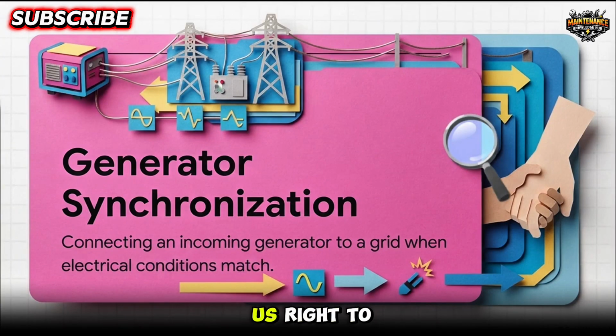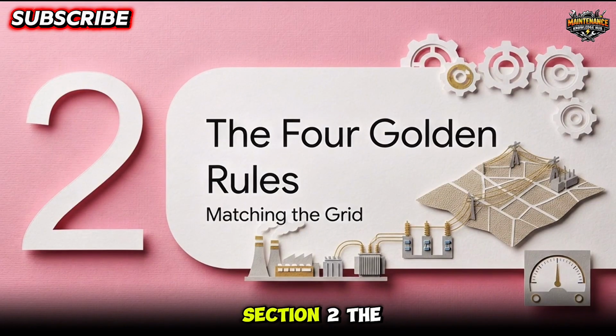And that brings us right to our core definition. Generator synchronization is the process of connecting an incoming generator to an energized electrical grid only when its electrical conditions perfectly match the grid's conditions. So the really crucial takeaway here is that matching is the ultimate goal. The generator essentially has to mimic the grid flawlessly before they are allowed to electrically hold hands. Moving on to Section 2, the 4 golden rules.